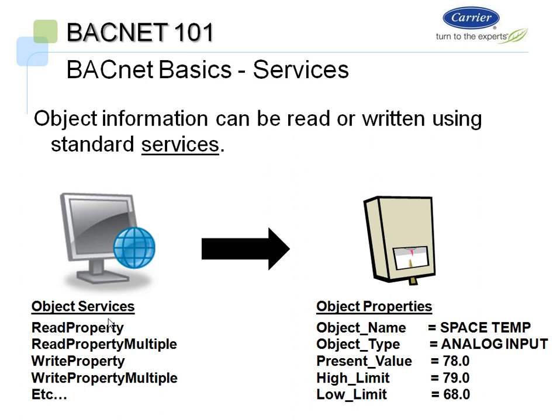So a read property value service would be used to read the object of space temperature, to read the present value of it. So if you wanted to read a space temperature of a rooftop unit on your system, you would use a read property to read that value. Now, if you wanted to take an outdoor air temperature reading, say, on one of your controllers, and you wanted to use that reading, that value on another controller, you would use a write property in order to do that. These are the object services that BACnet defines, and there are a few more, but the main ones you need to use are read and write, and that is how you communicate objects throughout the system.